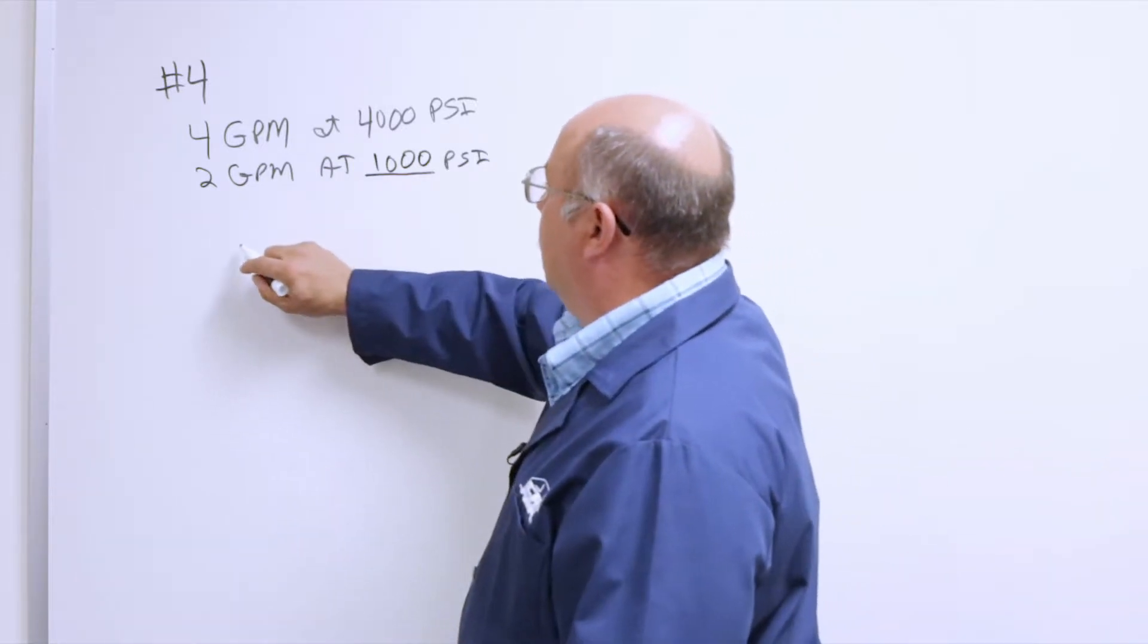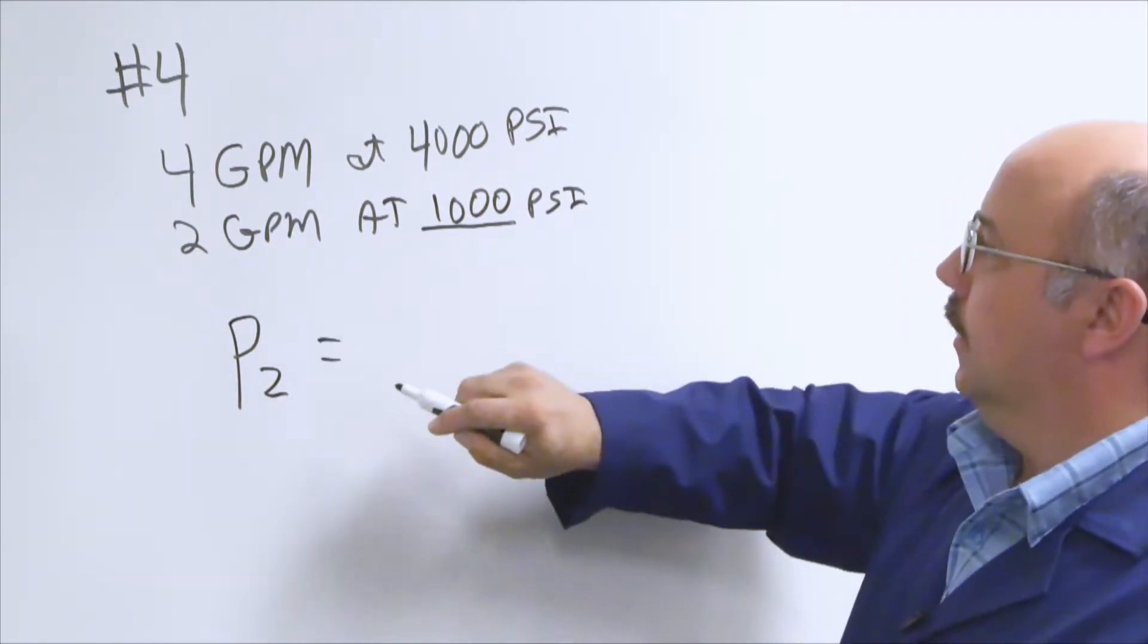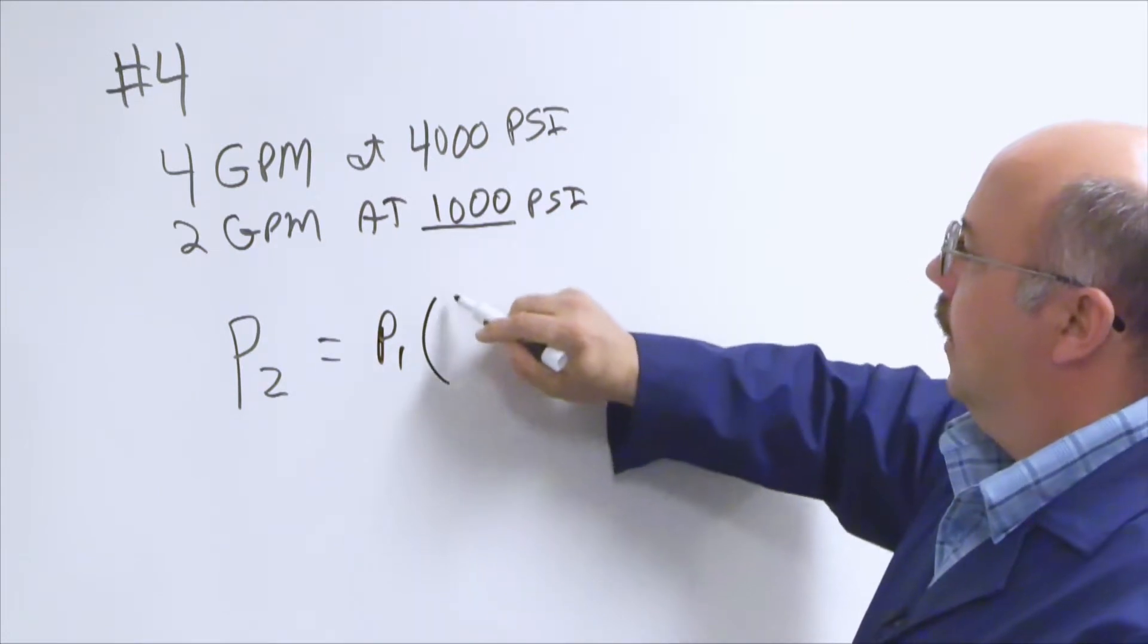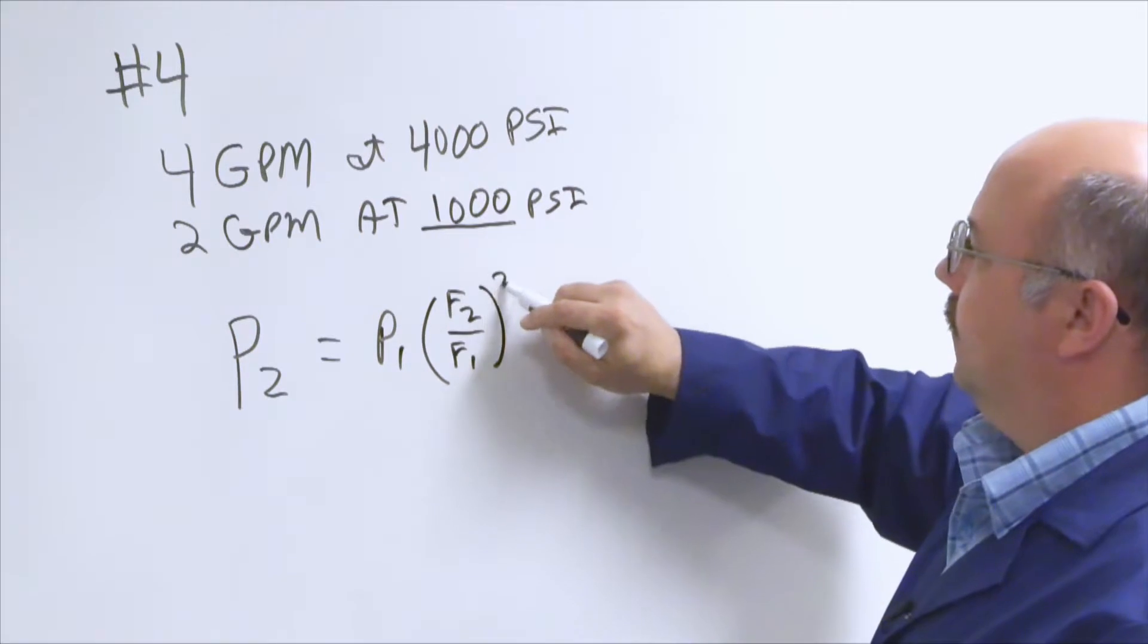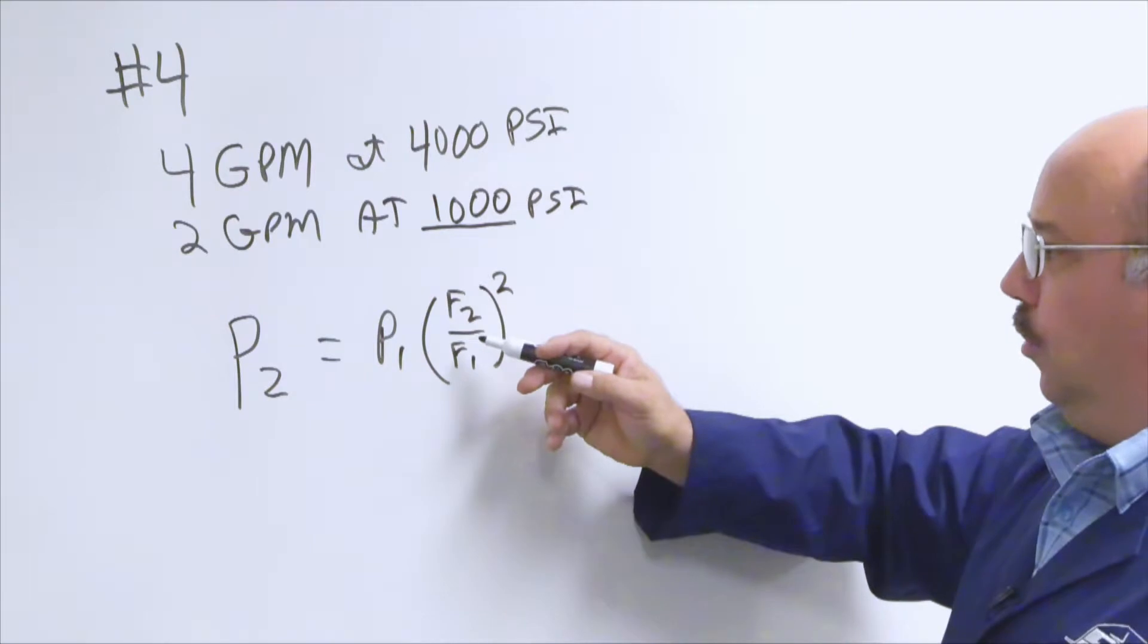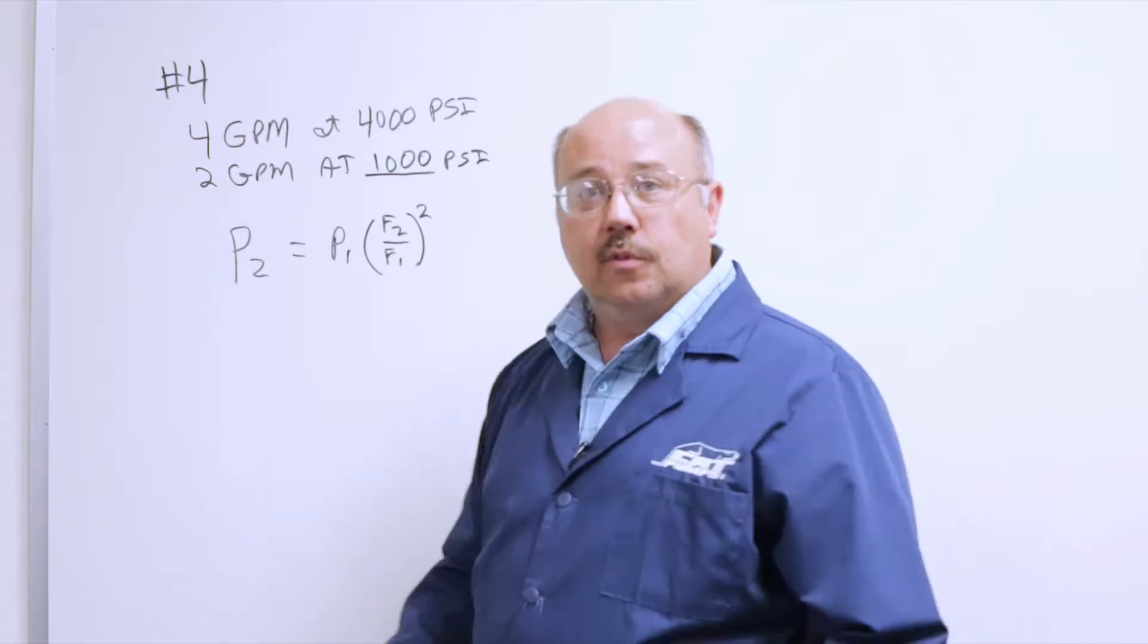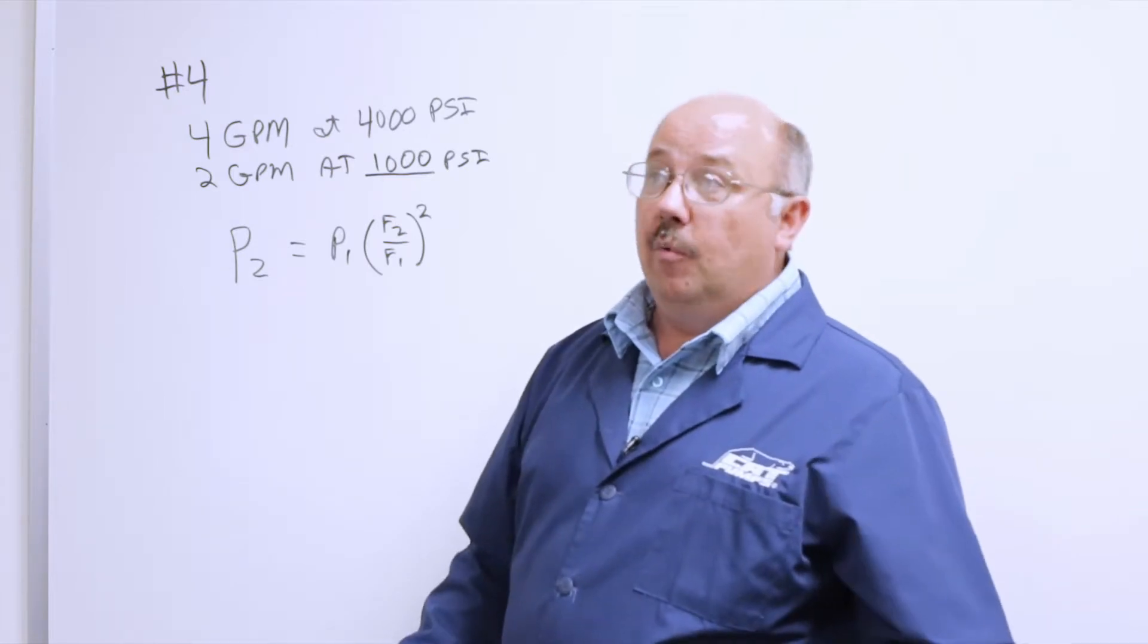And so we have to be able to explain that in a formula for doing calculations. The formula comes out that P2 equals P1 times the ratio F2 over F1, and then this is squared. So if we throw the numbers in there, we get 4 over 2, which is 2, square that, we get 4. 4 times 1,000 is 4,000. So the formula works out.